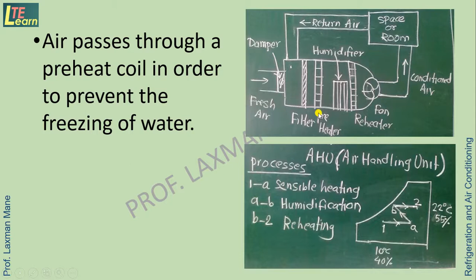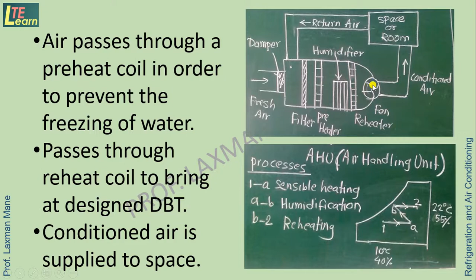So these processes can be understood by using psychrometric chart diagram. Here process 1 to A is taking place, sensible heating. Then A to B is humidification and B to 2 is reheating. So 1 to A is a process taking place in a preheater, A to B humidification process takes place in humidifier and B to 2 process takes place at reheater. So at the end, conditioned air is supplied to the space by using the fan, by using this duct, that is supply duct.